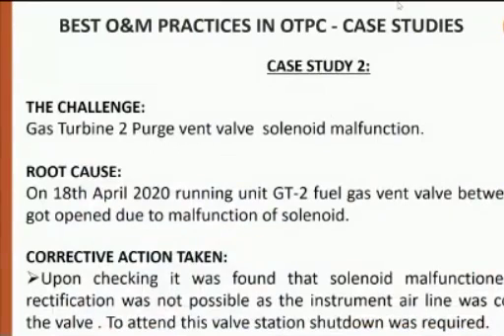This is another case study. Basically, we observed that one of the pulse valves got opened while the gas turbine was in operation. This purge valve only comes into the picture when there is purging of the entrapped gas during startup. It should not open while the machine is running. So we went to the field and observed that one solenoid had malfunctioned.